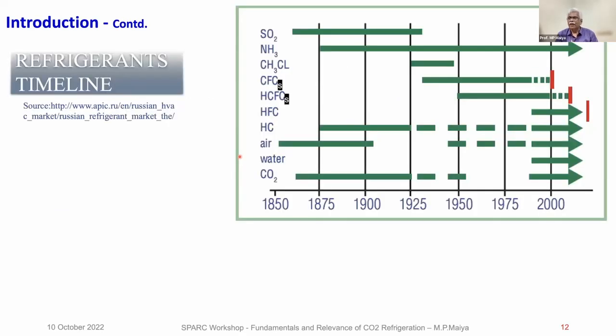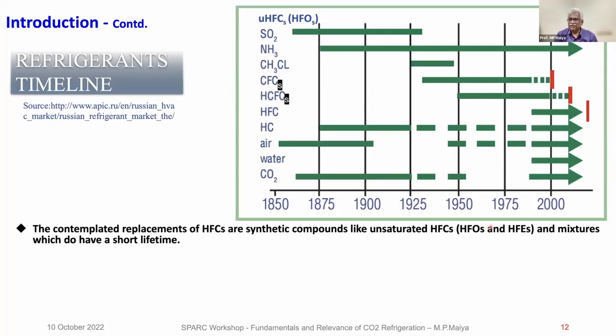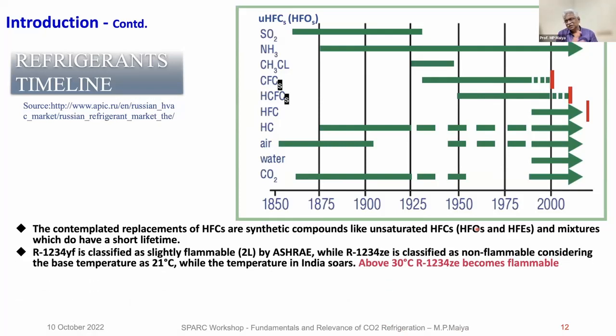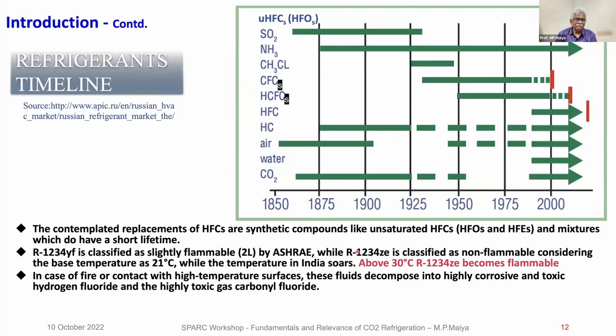You can see the use of refrigerants. We can see all these have gone now. Hydrocarbon has gone in between and has come back. Now unsaturated hydrofluorocarbons, or HFOs, are introduced as a replacement for HFCs. They are introduced, but you can see a lot of problems with the HFOs. They are kept on the back burner, but they are introduced. They are flammable, a lot of problems with that. It becomes a highly toxic gas when it comes into contact with a hot surface. When it burns, let's say an automobile is going through a big tunnel and something happens, poisonous gas will be released.